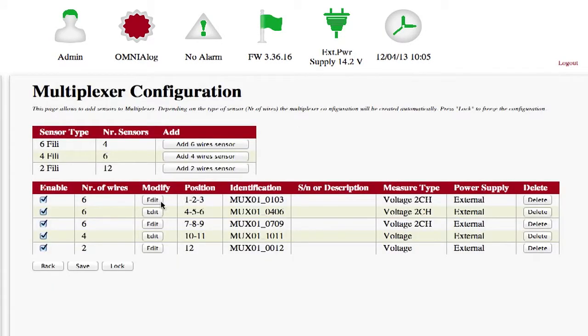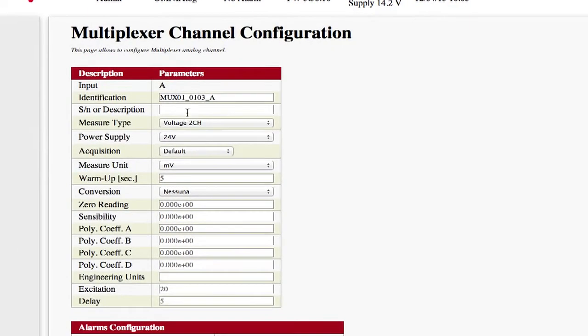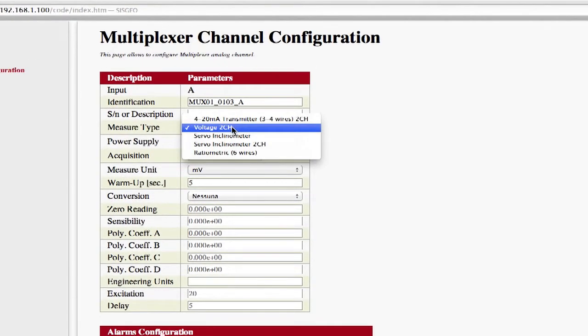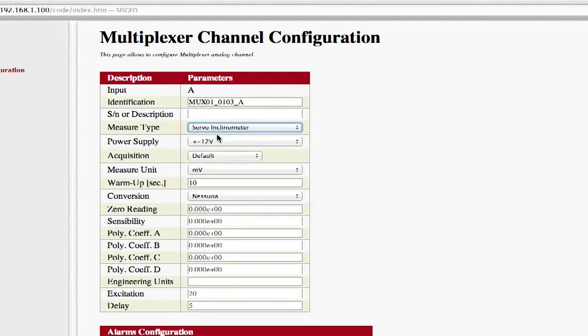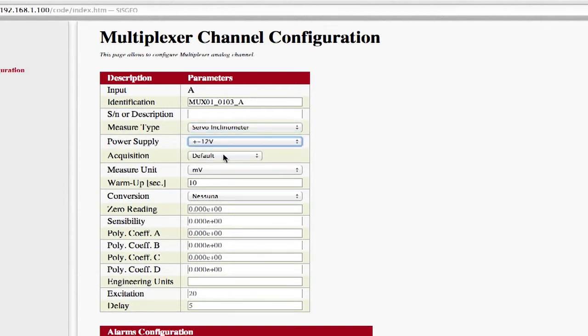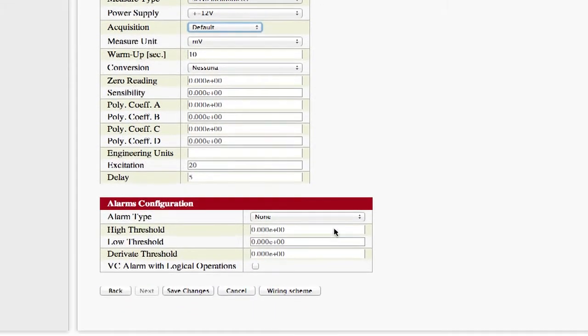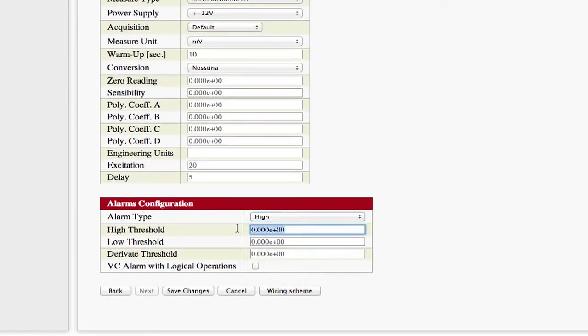Enable the channels and press Edit to configure the channel. A new page called Multiplexer Channel Configuration will open, on which it is possible to configure all the parameters of the acquisition channel in a totally analog manner, as done for the analog channels. Based upon the type of measurement chosen in the measurement type field, the default settings recommended by Sisgeo will be loaded for the underlying fields. It is also possible to choose different parameters or edit the default values. Once the configuration has finished, press the Save Changes button to confirm.